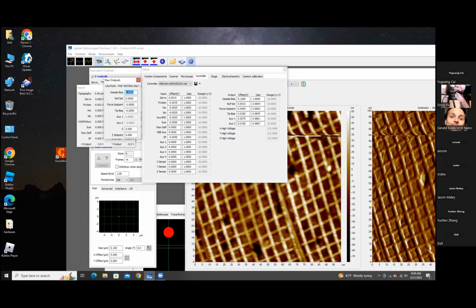5.07. So 5.07. I'm going to give you a speed trick on this one, but I'm going to give you the math first. The math is you take your known value, divide it by your measured value, and then multiply that by your current gain value for your new gain value. I see. So again, it's your known value divided by your measured value times your current gain. Well, we know that our gain is 1. Anything times 1 is itself, so we can eliminate part of our equation here. Wrong side. You want to be on the sample bias. No, sample bias, yes. There you go.